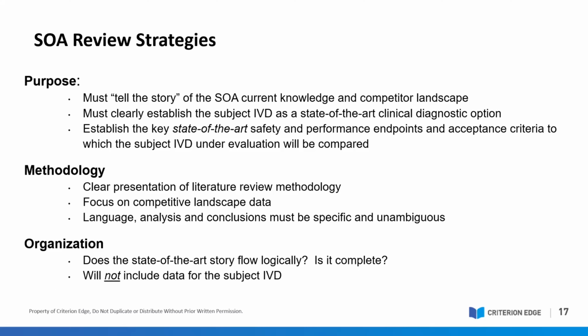It could include publications from respected authorities in the field or clinical guidelines, or really any other information for similar products on the market. And then it's also expected to compare the benefits and risks of the device under development with the benefits and risks of similar devices available on the market.